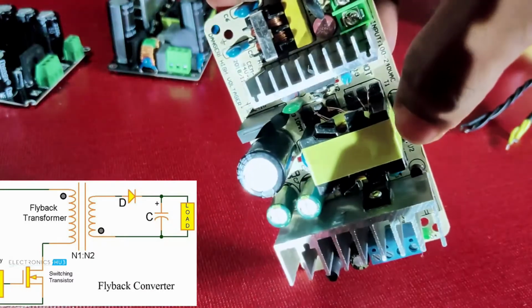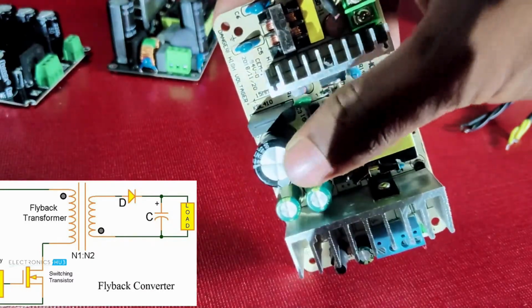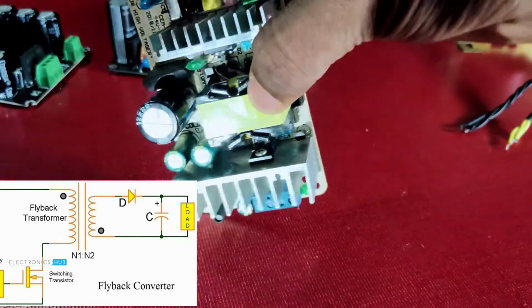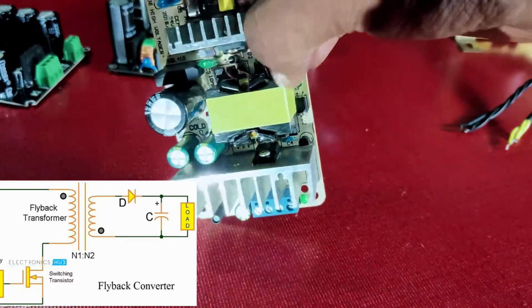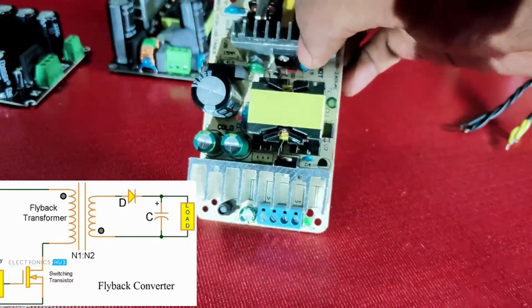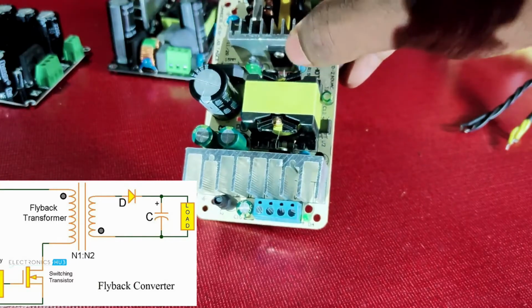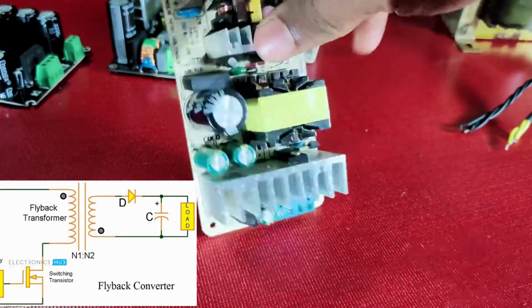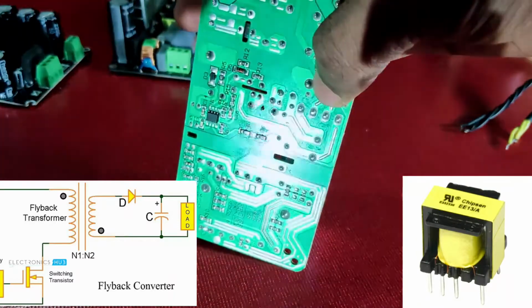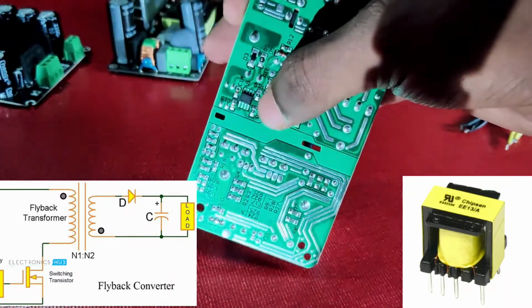This 325 volt DC is supplied to the high frequency transformer next to it. In order to convert the DC into high frequency pulses, we need a power switch, since transformers should not be used with DC. This flyback transformer is responsible for the isolation as well as the voltage reduction.